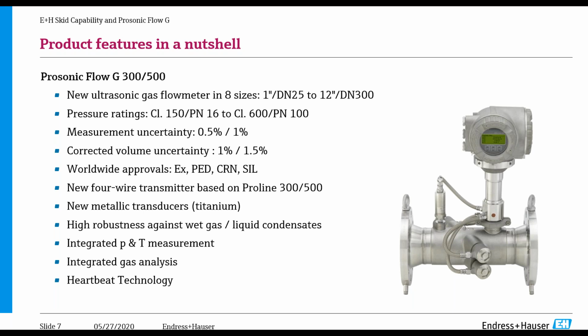Now that is non-corrected volume flow. For corrected volume flow, where you're compensating for pressure and temperature, the uncertainty is 1% with our premium calibration and 1.5% with our standard calibration. The meter has worldwide approvals, so it can go into hazardous locations, obviously, and we also have some approvals on the strength of the meter body versus pressure. And we also have the SIL approval, which is safety integrity level, for safety critical loops. We have a mains power supply transmitter.